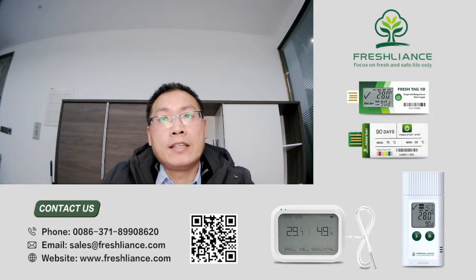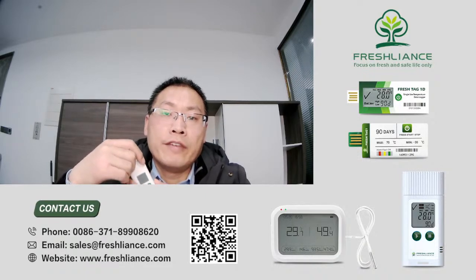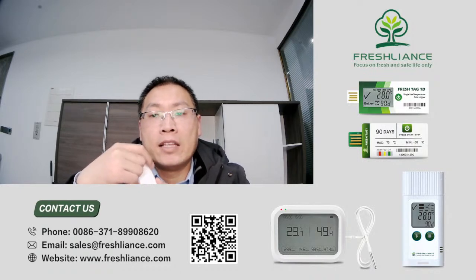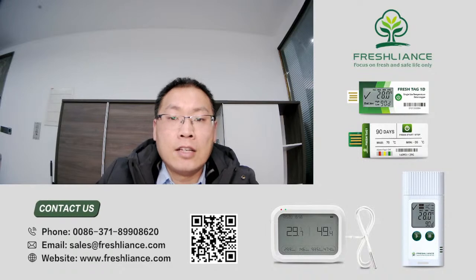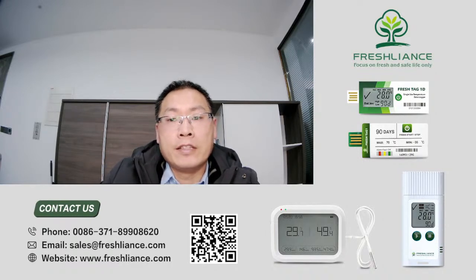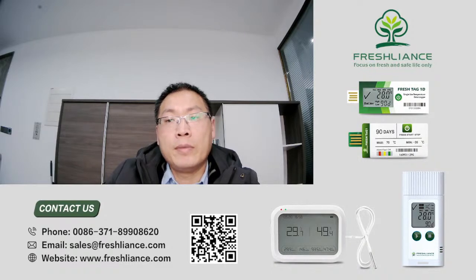From the Freshliance tools, you can also configure the suitable time rules, time format, logging interval and logging duration here. Just be noticed that the longer the interval you set, the more power savings, and then the logging duration will be longer.